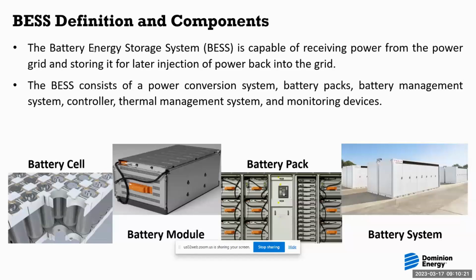The battery management system monitors the batteries to make sure individual cell voltages are balanced, charging happens properly, and temperature is controlled. There's also a controller, which is the brains of the system, telling things when to charge and discharge; a thermal management system to exhaust heat from charging and discharging; and monitoring devices. In electrical power systems, we always have monitoring devices to make sure things trip offline when they're supposed to.